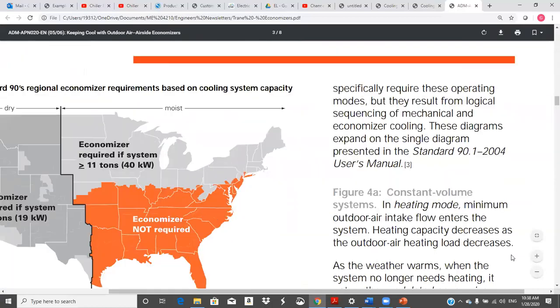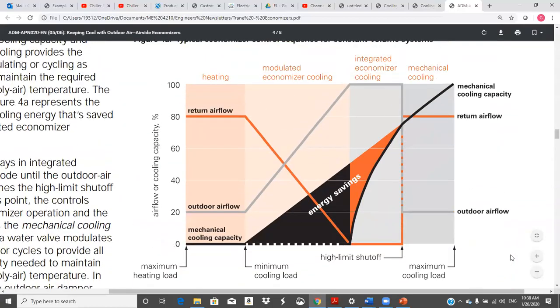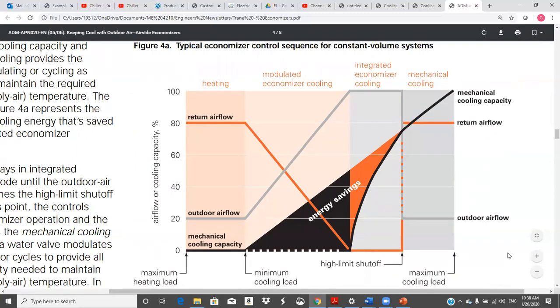Now let's finish down here. I don't know who came up with this diagram, but it's a pretty good diagram. It pretty much shows it. What's happening here is we've had to start mechanical cooling. This is mechanical cooling capacity because the outside air is just not cold enough to do it, right? But we're staying on 100% ventilation air because the enthalpy of this is less than the enthalpy of the return air. And finally, we get up to some point and that switches, and we go, oh no, we don't want any more of that stuff than we have to have. It's too energetic. We'd rather have return air.